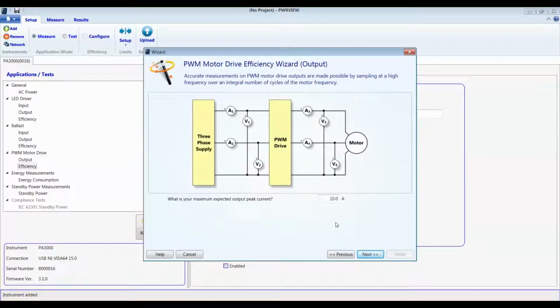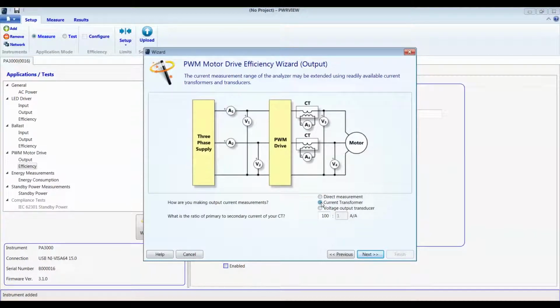Let's enter 3 amps for the output as well and click next. This again is a direct measurement as our current is lower than 30 amps. Now, if we had a current higher than 30 amps, we would use one of the high accuracy current transducers. In that case, we can select the current transducer options and set the scaling ratio as required. For now, we will stick with direct measurements, and click next.